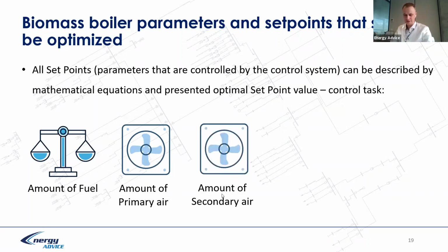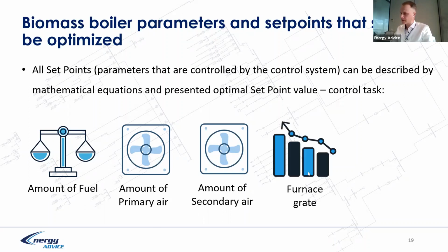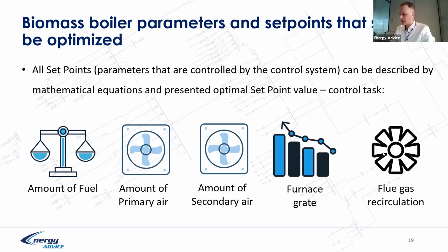Secondary air, generally it is related to oxygen level measurement. However, how we make impact on this, we simply understand that the fuel is burned fully and perfectly, and the oxygen meter is metering well or not well. What is a metering error? If we have furnace with a grate, we can make impact on movement. And if you have flue gas recirculation, for example, we can make impact to the recirculation.